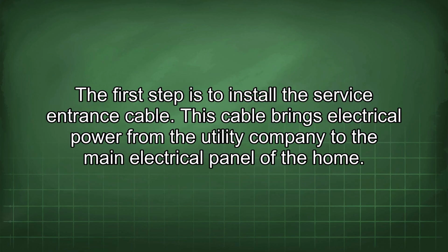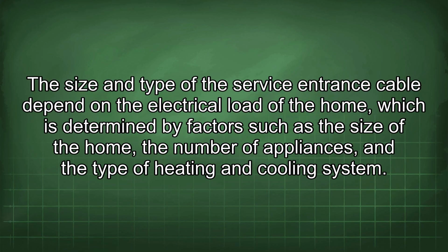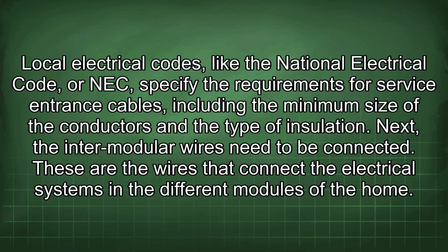The first step is to install the service entrance cable, which brings electrical power from the utility company to the main electrical panel of the home. The size and type of the service entrance cable depend on the electrical load of the home, determined by factors such as the size of the home, the number of appliances, and the type of heating and cooling system. Local electrical codes, like the National Electrical Code, or NEC, specify the requirements for service entrance cables, including the minimum size of the conductors and the type of insulation.